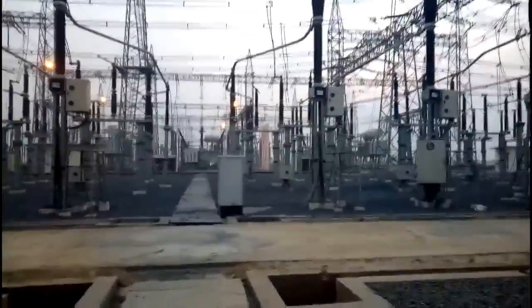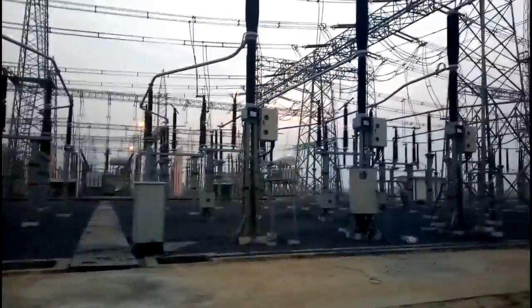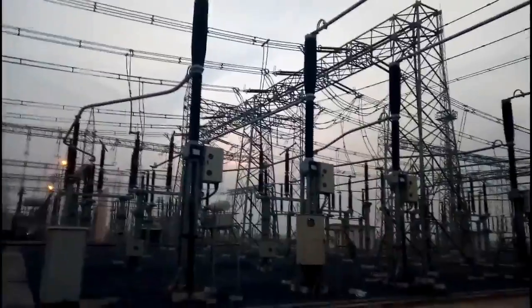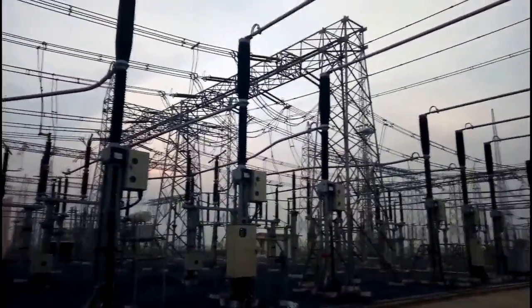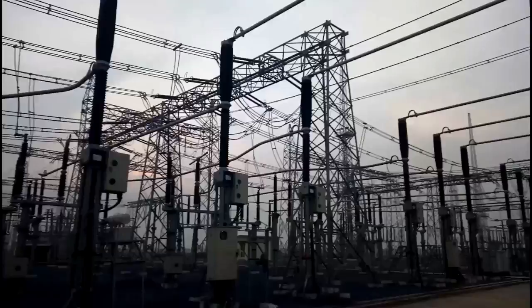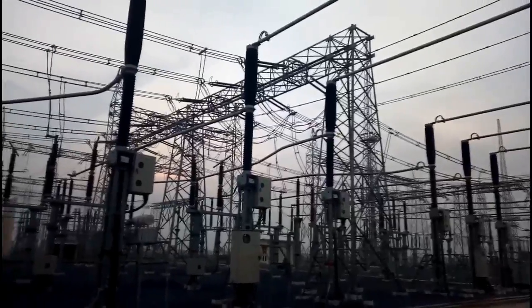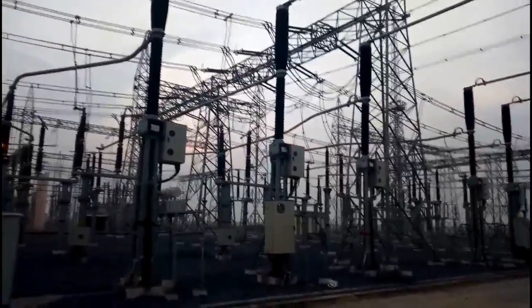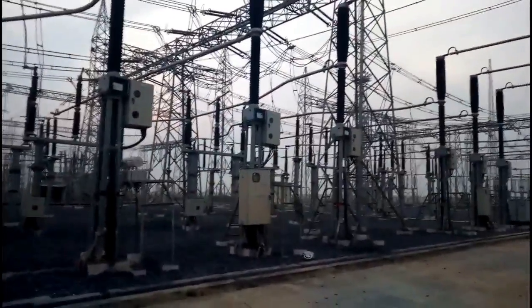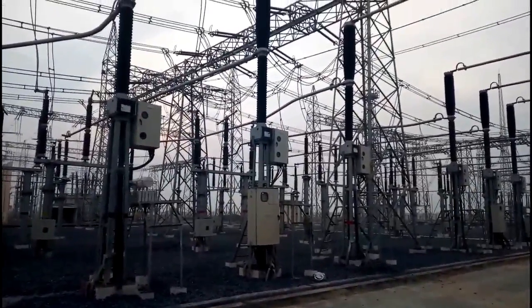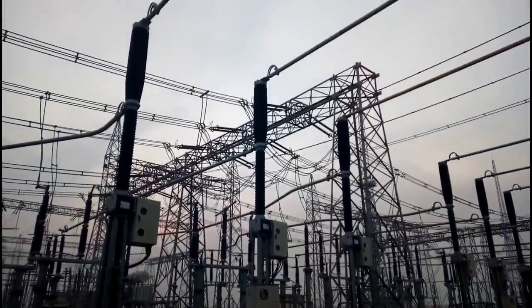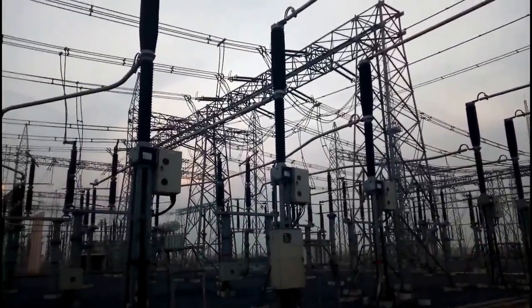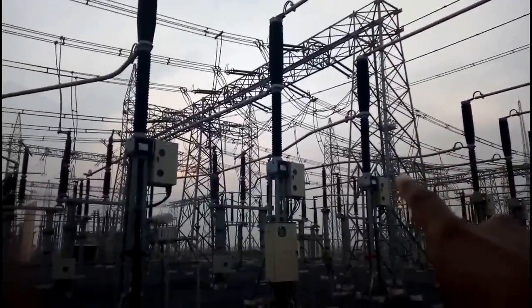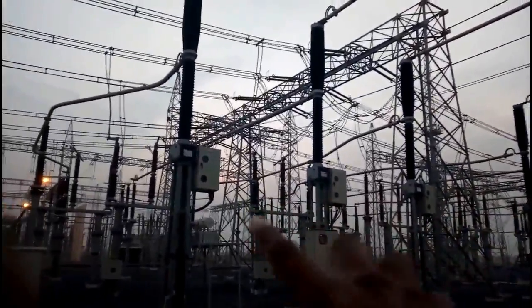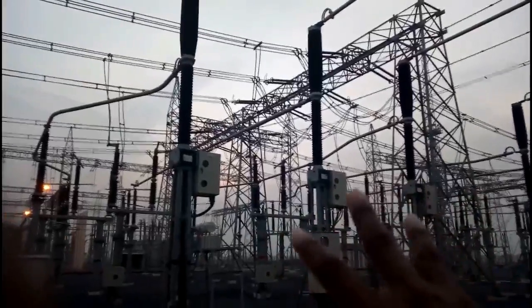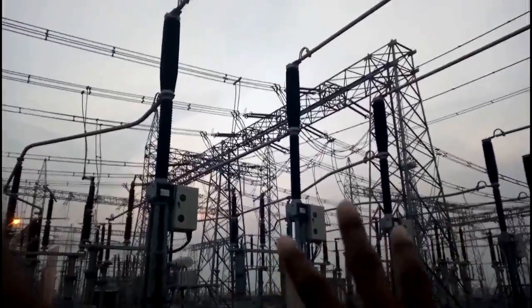Now one more thing I would like to explain, that the isolator is an offload device. Offload device in the sense that in off condition, there is no power supply, the line is not energized. In such a situation only we can operate it. And this is the equipment you are looking at. This is called a circuit breaker. You would have heard about the circuit breaker. You can check there, that is R phase, Y phase, and B phase. This three-phase equipment is the circuit breaker.